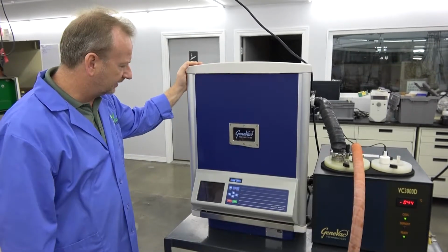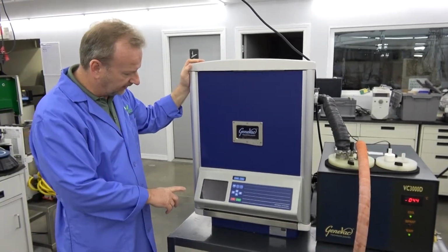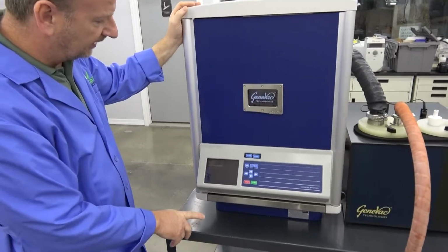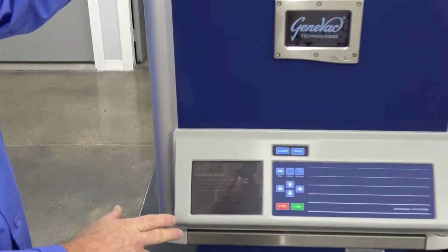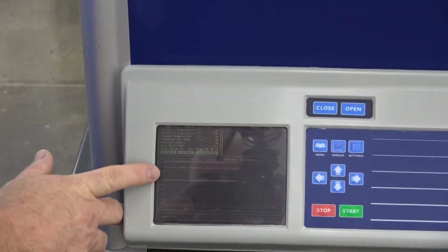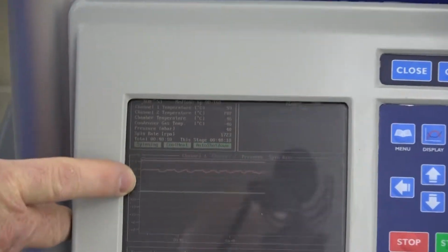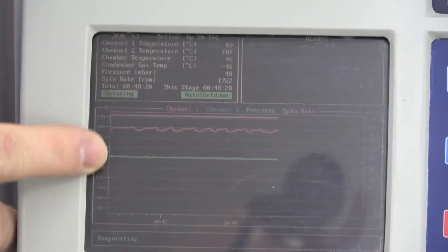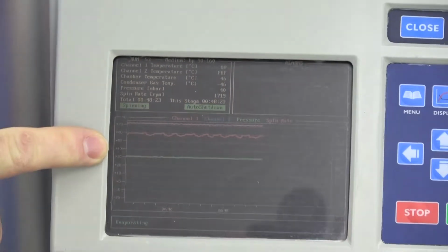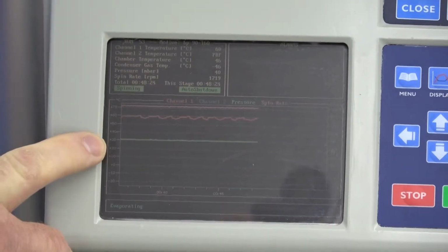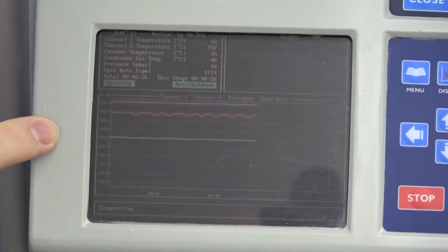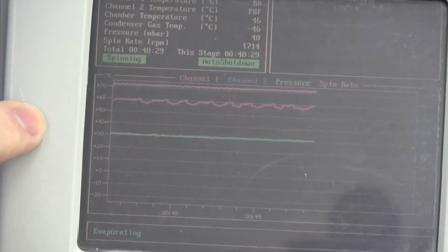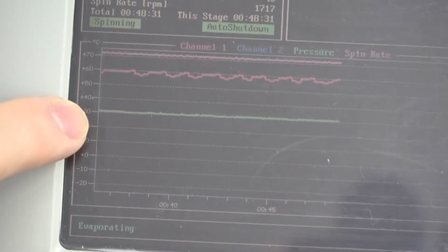Right now I'm just going to come up and have you take a look at the screen. It's a little hard because we've got all the lights on in the shop and there's a bit of a glare, but you're going to be able to see at least these three lines. This is just monitoring the system as it runs. The bottom line running across is the vacuum, which I've got set at around 40 millibar. And it's running very consistent on the vacuum.